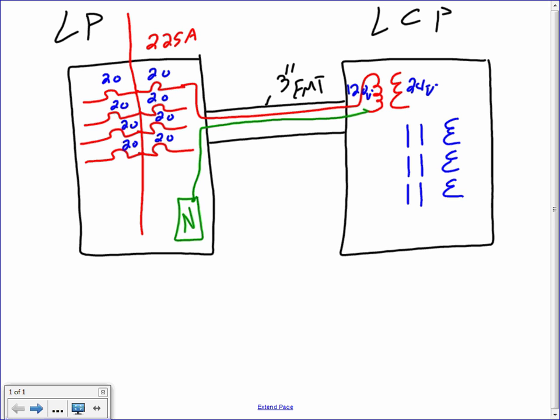These 24 volts have 2 functions. Function number 1 is to power the electronics inside the lighting control panel, right? They need power, juice. Function number 2 is to get you the 24 volt to the switch. So when you turn things on and off, you get 24 volts because you don't use 120. That's what a lighting control panel is.